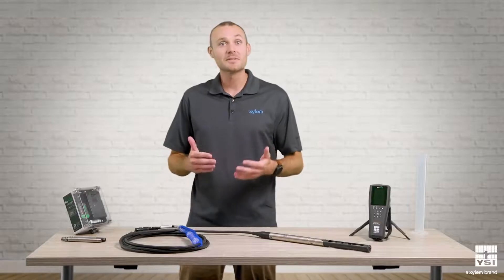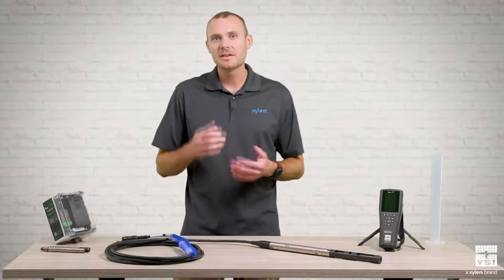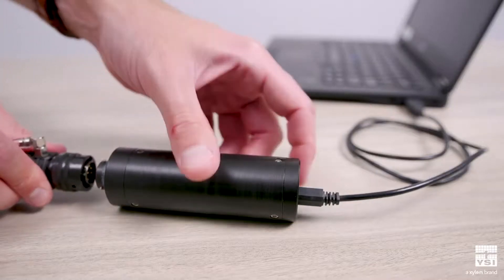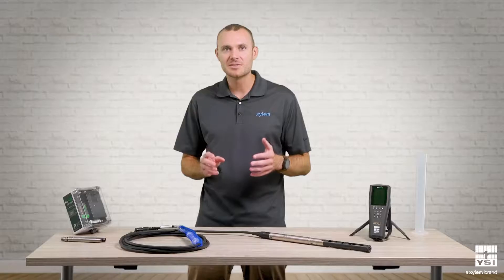Next, let's look at some accessories for interfacing with the ProSwap logger. There are two primary options. One is a ProSwap handheld meter — this is a great portable option for checking live data, retrieving logged data, and setting up deployments on the go. You can also use a ProDSS handheld. The second option is a USB adapter, which allows you to interface with the ProSwap logger using Kor software. Kor is a powerful software tool that makes it easy to calibrate sensors, set up deployments, and manage data.